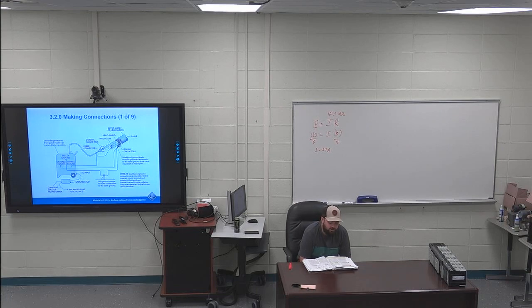So all you want to get out of that is that your high pot is using a 120 volt source. You're also going to need a voltage regulator, so your regulator that moves your voltage, like your tens of thousands of volts, higher and higher. On page 35, that last full paragraph right before that little bit of math, the whole thing's highlighted. The use of a line voltage regulator under such conditions greatly increases the usefulness and ease of operation of the equipment. In general, the power rating of the regulator should be based on the maximum power output capability of the tester multiplied by a factor of about 1.3.